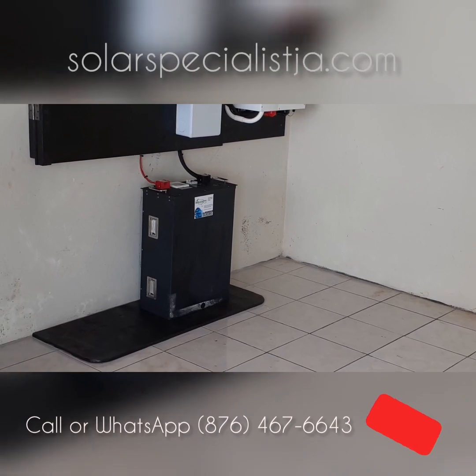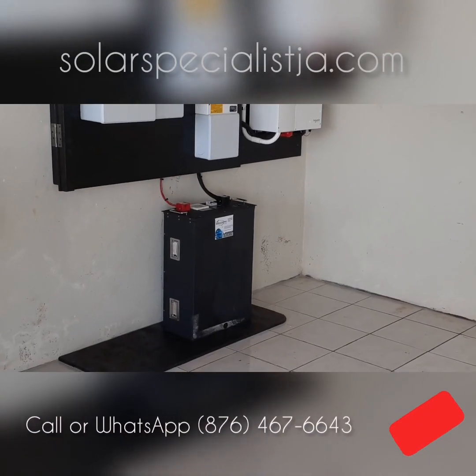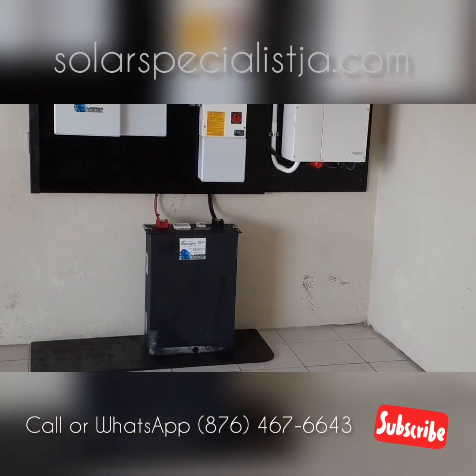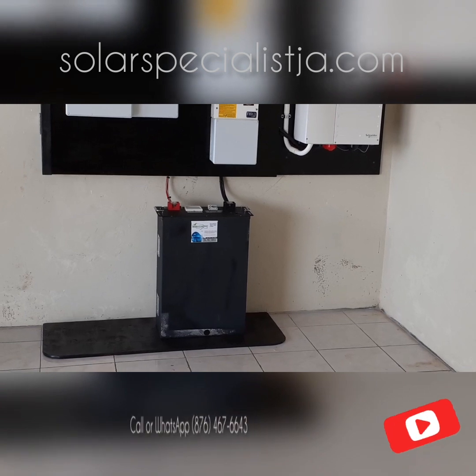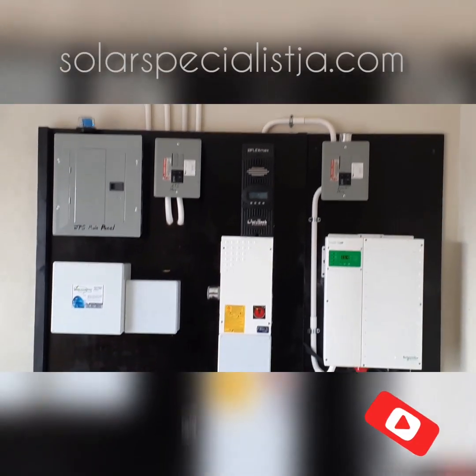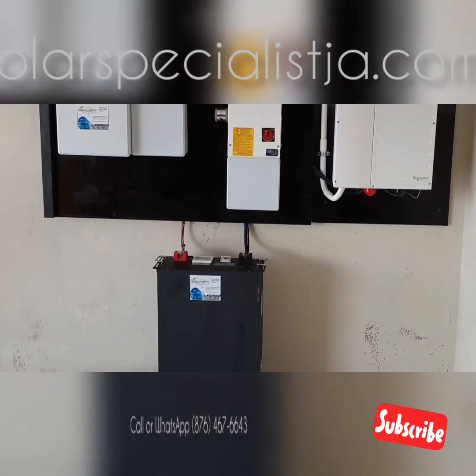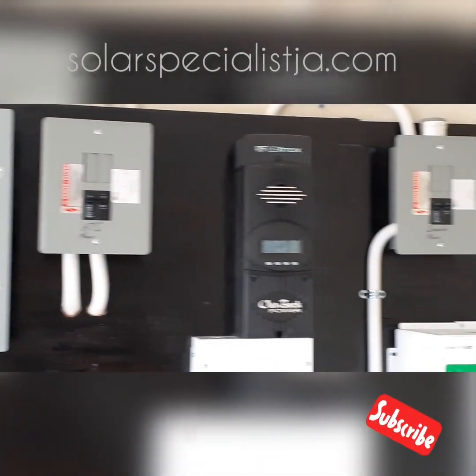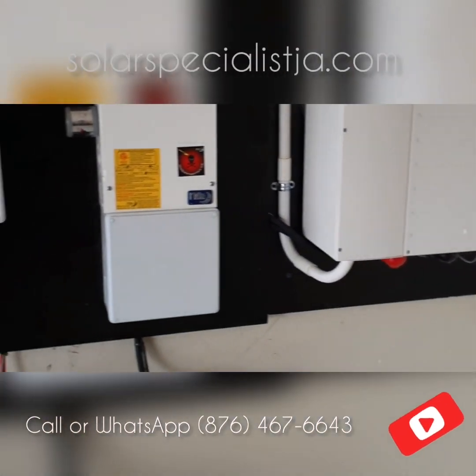That 10 kilowatt hour lithium battery would basically replace about eight lead acid batteries, so you can see how much space you can save. Lithium not only saves space but it's also a much longer lasting battery — it will have a lot more charge and discharge cycles than an AGM, flooded lead acid, or sealed lead acid battery. A good quality lead acid battery is usually rated around 1,300 to 1,500 cycles, whereas a lithium battery is normally 3,000 to 5,000 or 6,000 cycles.